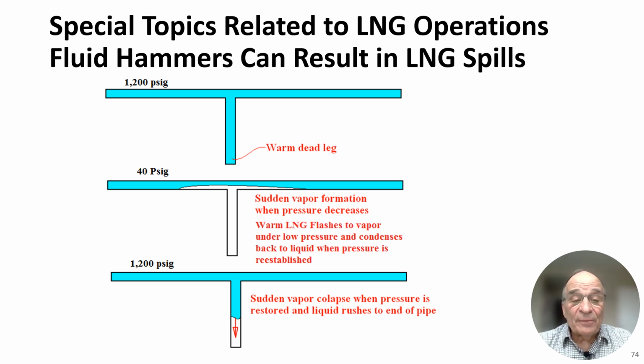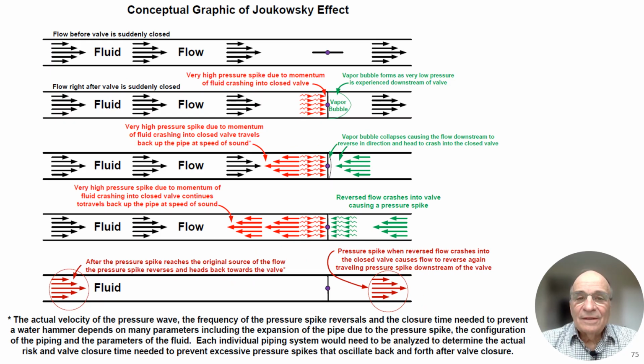Slowly. You bring up the pressure, you start the pumps on recycle, and you bring up the pressure slowly, which allows this section to fill up slowly. And then when it's totally up to operating pressure, you can then continue your operations. It's another type of water hammer, or I should say fluid hammer, that can happen. And that is the concept of the Joukowsky effect.